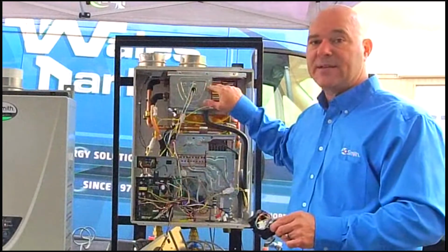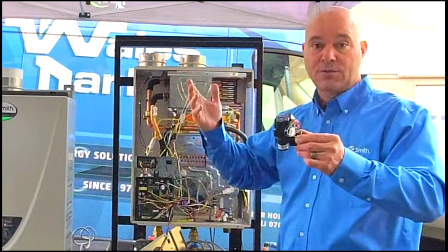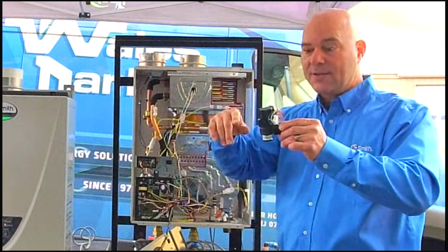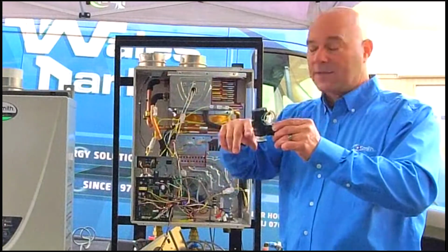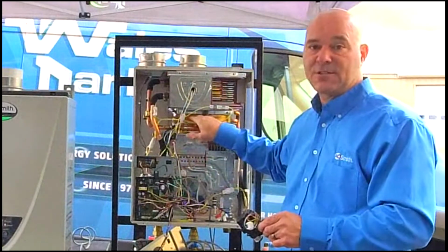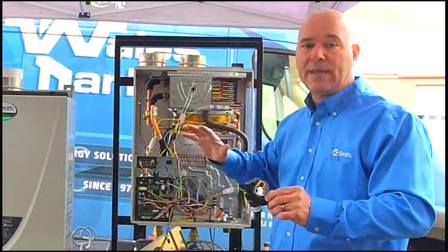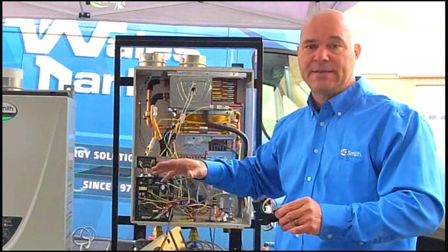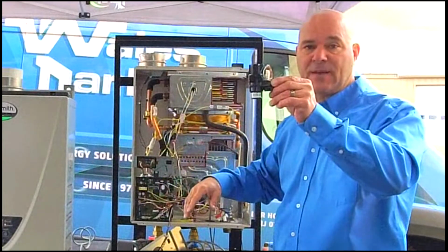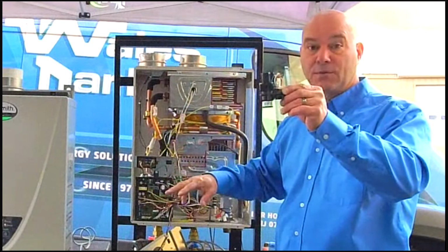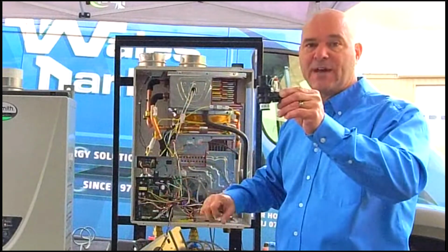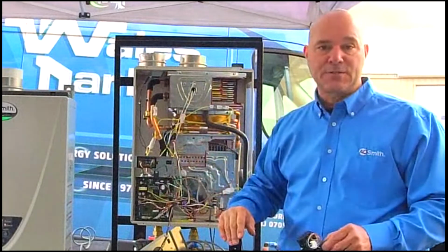If you don't elevate that temperature to over 120, 140 in that range, this will stay closed, and you're only going to have access to the primary heat exchanger. But that's only on the 540 and the CT 199. They're the ones with the bypass valve. The 140, 240, 340 don't have the bypass valve. You don't have to worry about elevating the temperature.